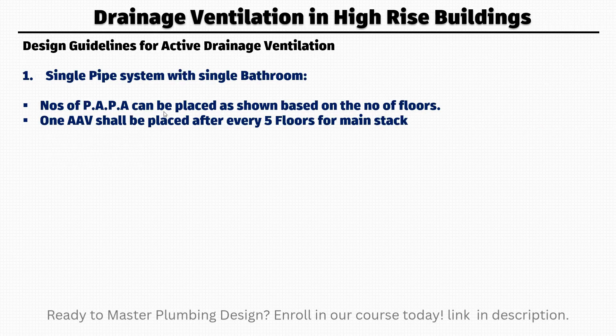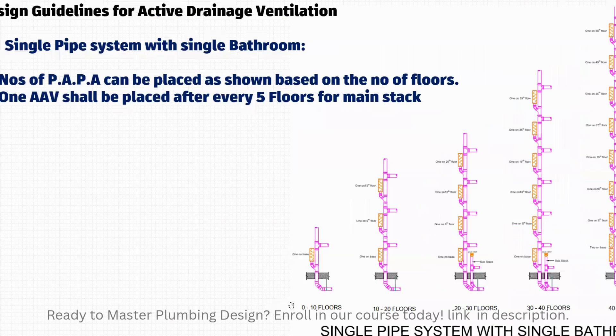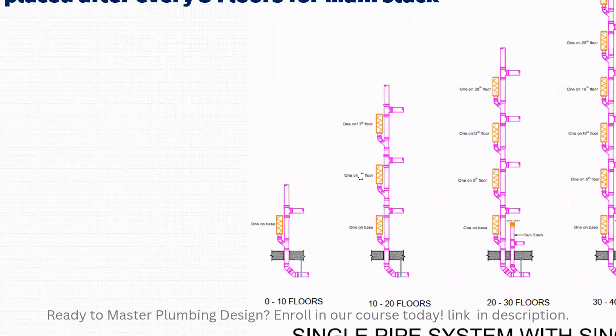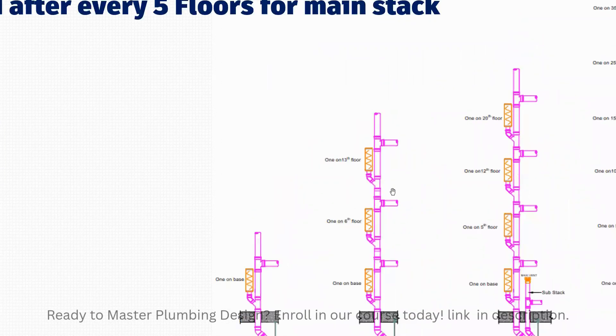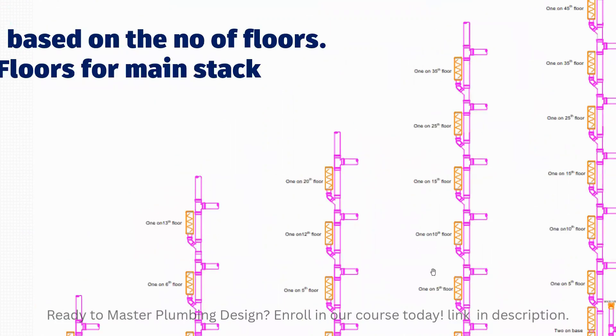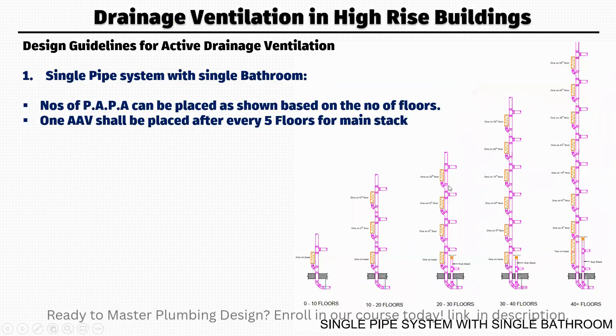Based on the number of floors, as you can see in this picture, there are different floor ranges: zero to ten, ten to twenty, twenty to thirty, thirty to forty, and forty plus. For zero to ten floors you need only one positive air pressure attenuator. For ten to twenty floors you need attenuators on the base, then on the sixth floor, then on the thirteenth floor. For thirty to forty floors you need one on the base, one on the fifth floor, one on the tenth, fifteenth, twenty-fifth, and thirty-fifth floor.